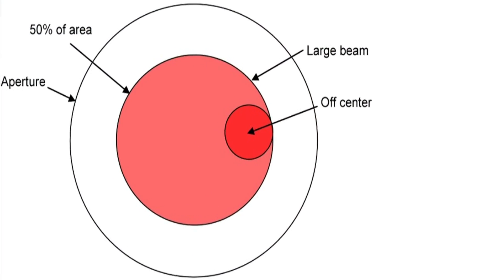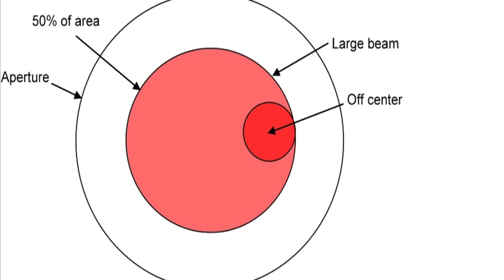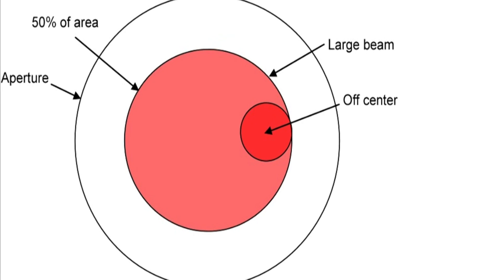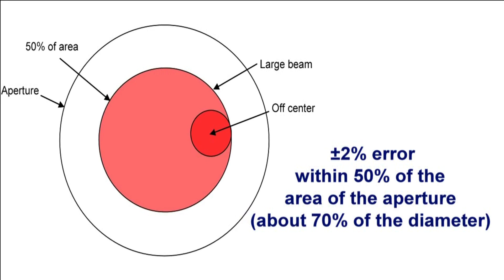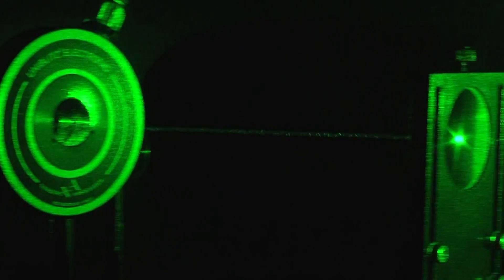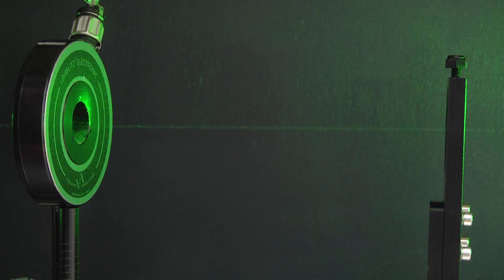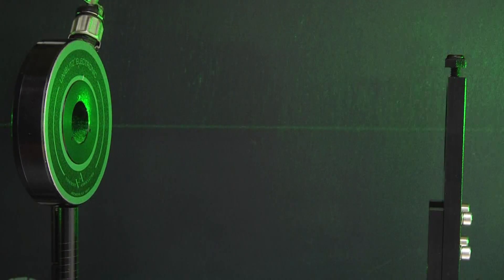Now we define usually, as you can see in this graph, that the maximum error for a beam that is off center is plus or minus two percent error within 50 percent of the area of the aperture or 70 percent of the diameter. If you carefully center the beam on your power meter, then you can usually ignore this source of error.